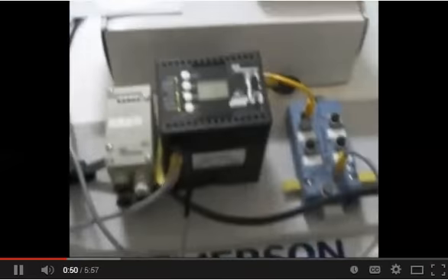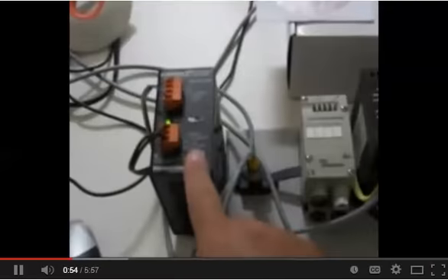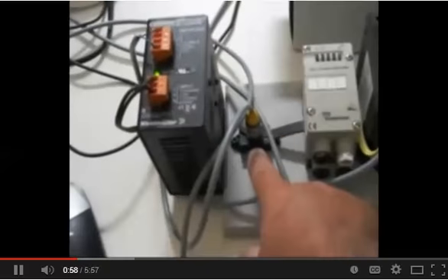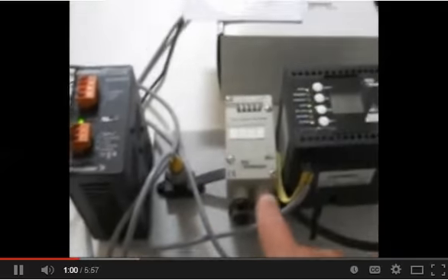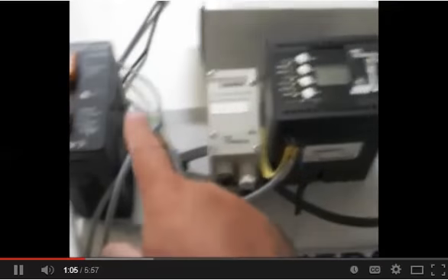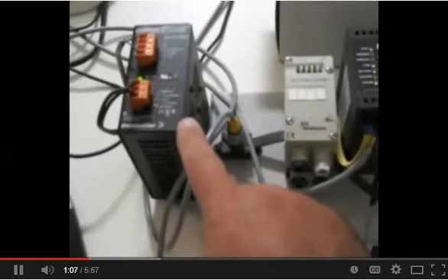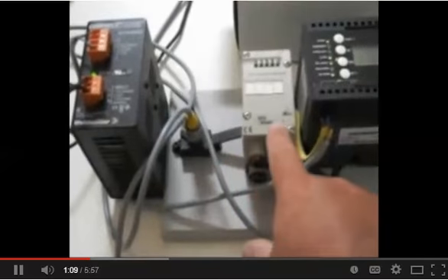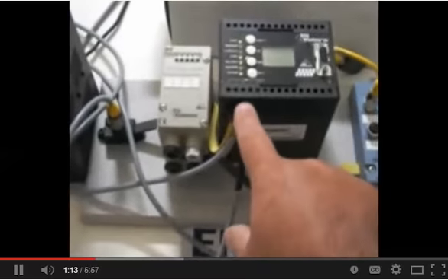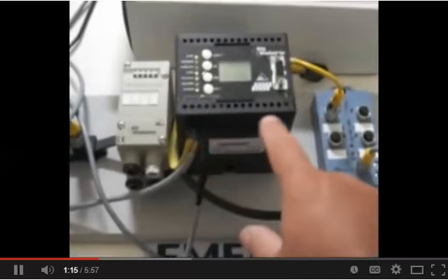Then our little demo system here, we've got a standard power supply connected right here, 20-volt DC power supply. We've got that wired into this connector here, which then goes into the Bihl Wiedemann power extender or conditioner here. That takes this standard power supply and converts it to an AS-i power supply. It decouples that supply for us. And then from there we've got that coming into our power network here on our AS-i master.